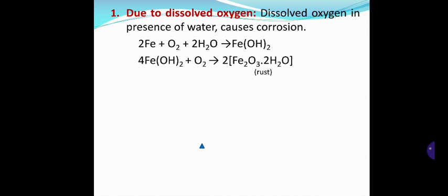The boiler corrosion caused by the presence of dissolved oxygen can be prevented by eliminating oxygen from the boiler water. Dissolved oxygen can be removed by several methods, by treating with sodium sulfite, or sodium thiosulfate, or many other reagents by adding them.